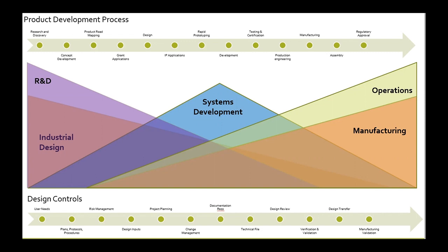I won't labour the point on this slide for today's presentation, other than to say that risk management applies effectively throughout the entire process, right back at the initial design controls formation stage in collating user needs, right through to manufacturing and volume deployment of the product. Risk management does apply. It's fairly light in the early stages. It's predominantly the planning and consideration of hazards and so forth right back at the start. And the core risk management activities kick in when the development process actually starts.